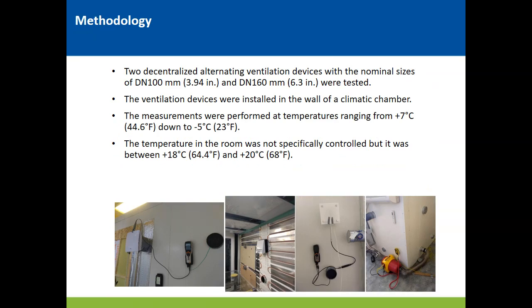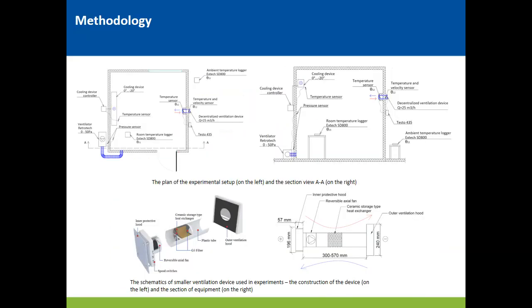If you don't know what these local decentralized ventilation systems are, I can shortly tell you they are small ventilation units that you place inside a wall. There is a section of it, and it consists of a small fan, a ceramic heat exchanger, a filter, and an inlet hood and outlet hood. Usually they are set up in pairs, so when one works in exhaust phase, the other works in supply phase. They are placed in the same room. They switch these phases every 70 seconds, so the ceramic heat exchanger heats up during the exhaust phase, and then during the supply phase it heats up the incoming air.